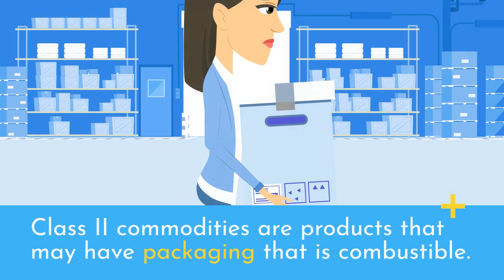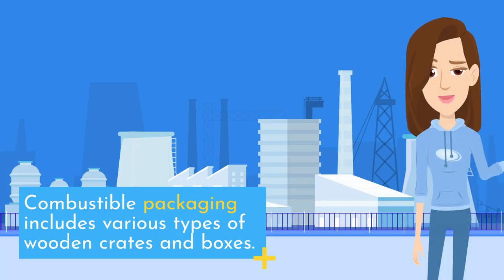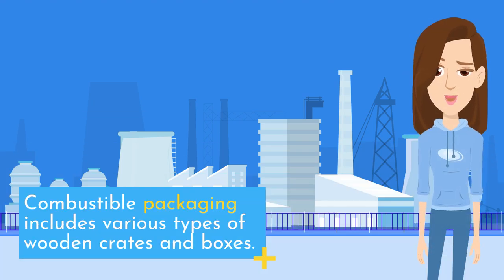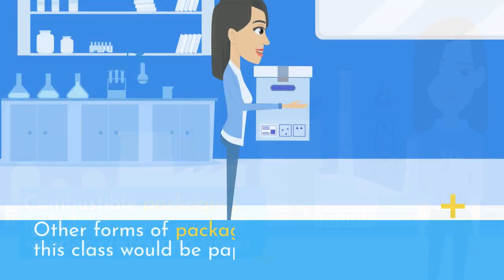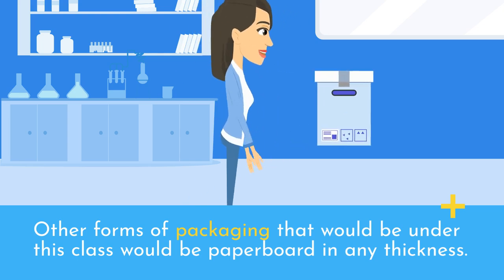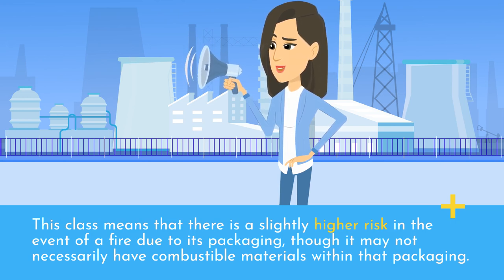Class II commodities are products that may have packaging that is combustible. Combustible packaging includes various types of wooden crates and boxes. Other forms of packaging under this class would be paperboard in any thickness. This class means there is a slightly higher fire risk due to its packaging, though the materials within may not necessarily be combustible.